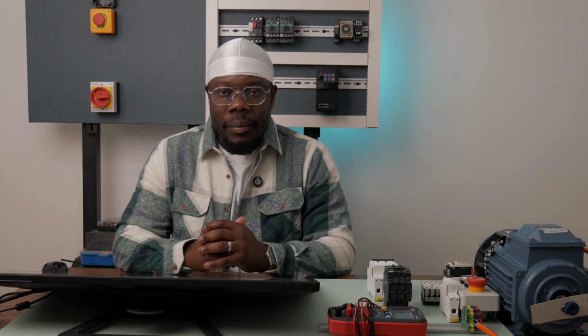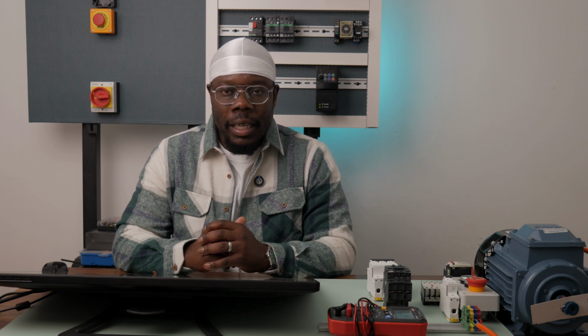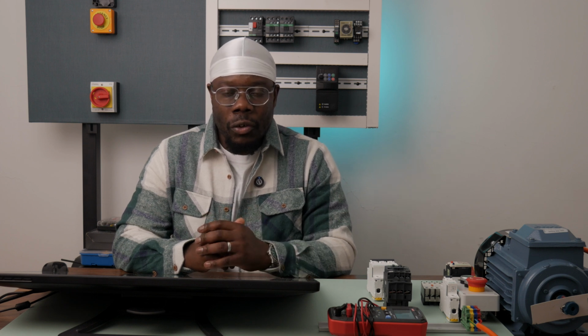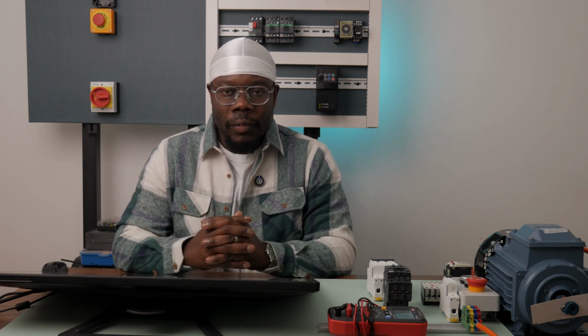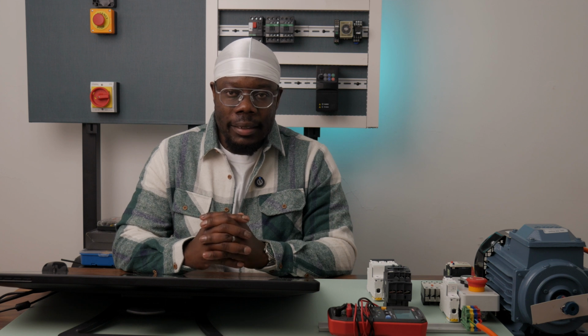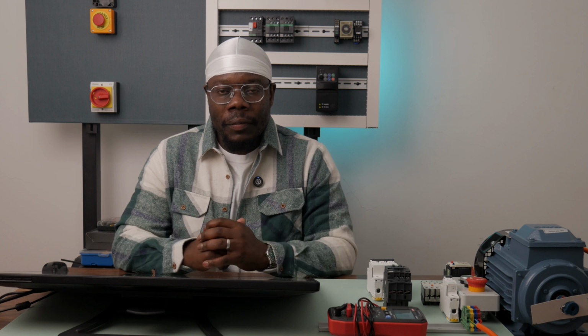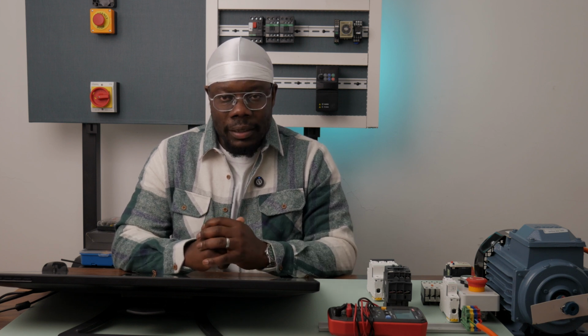encourage you to pay attention to this standard, because a lot of equipment that you are likely to come across, whether it was manufactured in Europe or most parts of Africa, is most likely to have schematics that are based on the IEC 60617 standard. So I encourage you to pay attention to this standard. Have a sound appreciation of the graphic symbols that are based on this standard.